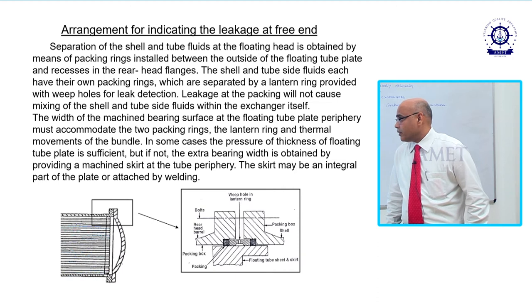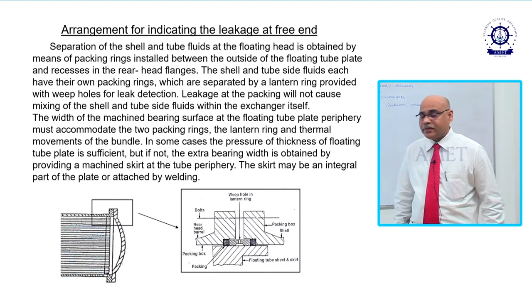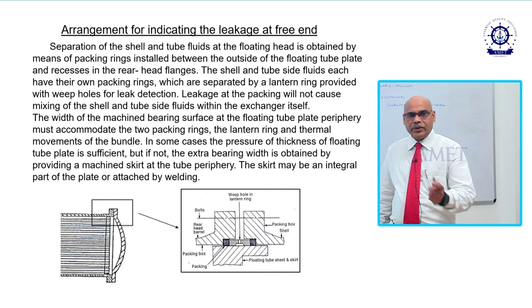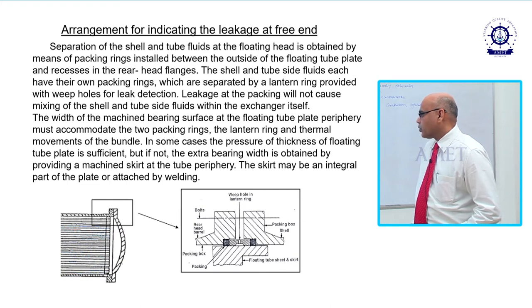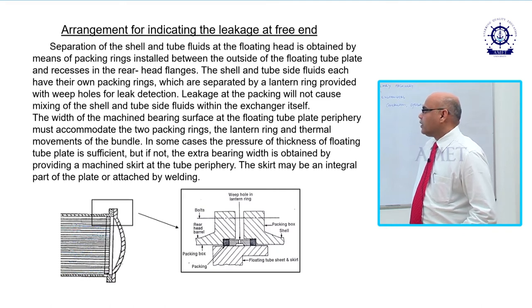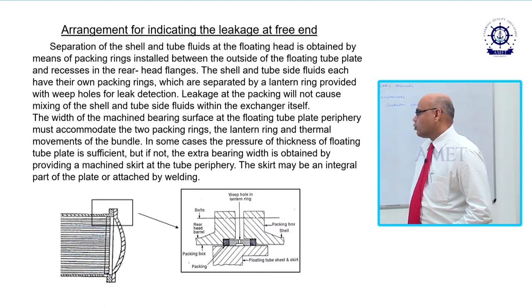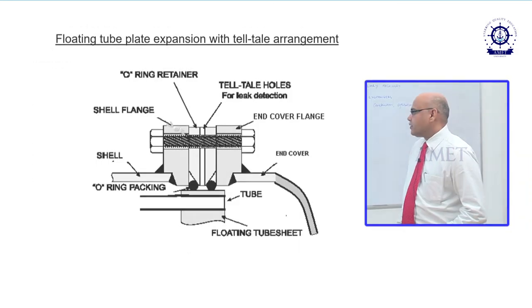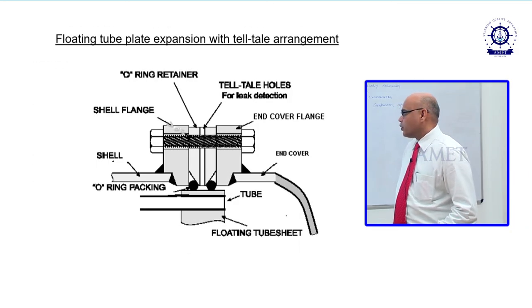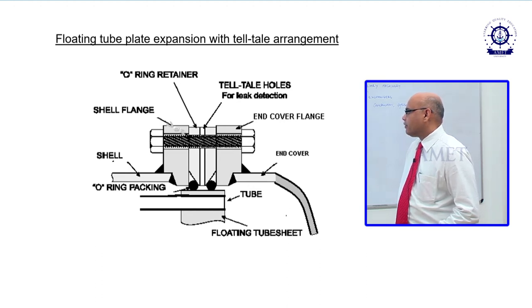Arrangement for indicating leakage at the free end: at the tube ends there are two O-rings which separate the two fluids, and in between there is a lantern ring with a hole. This prevents mixing of the two fluids. In the enlarged view, the two O-rings and a telltale hole allow any leaking fluid to come out visibly.